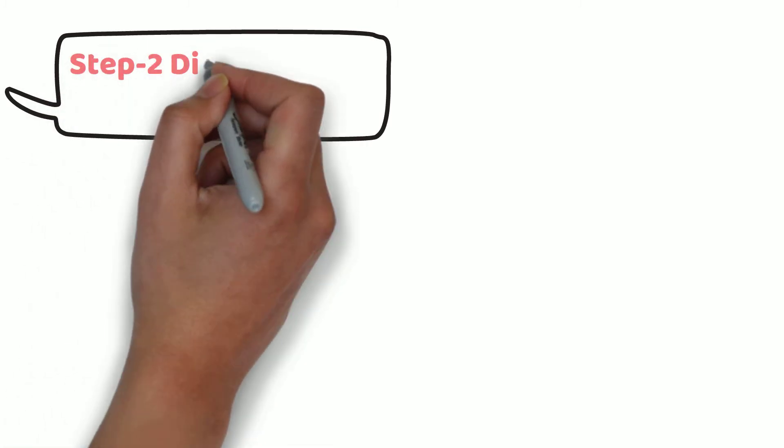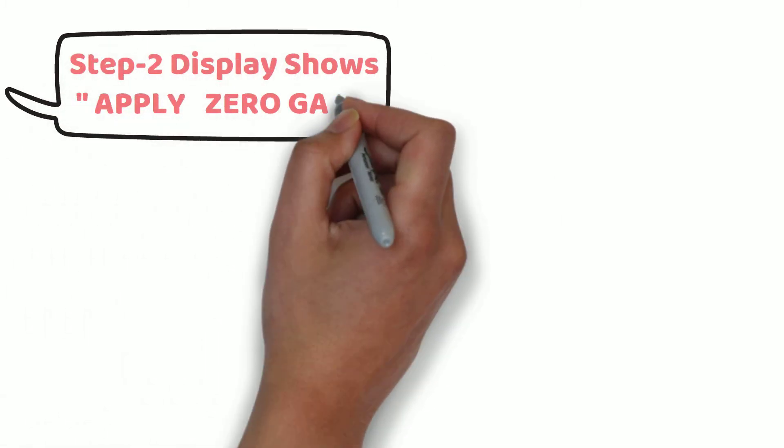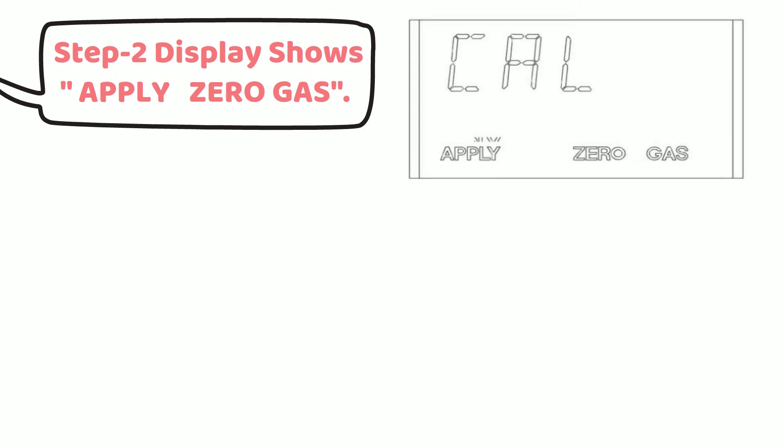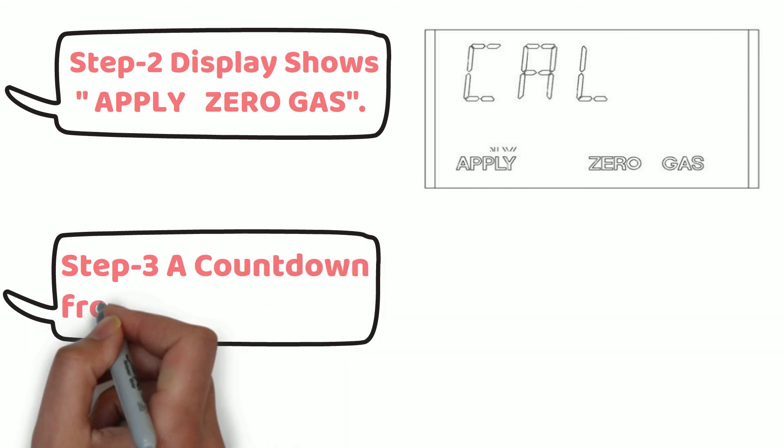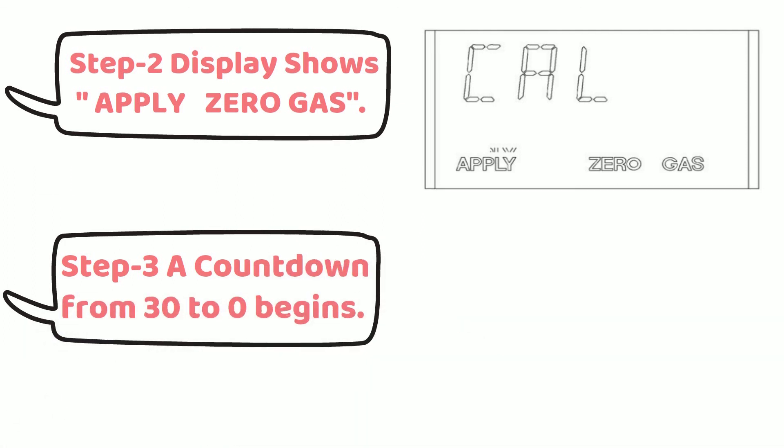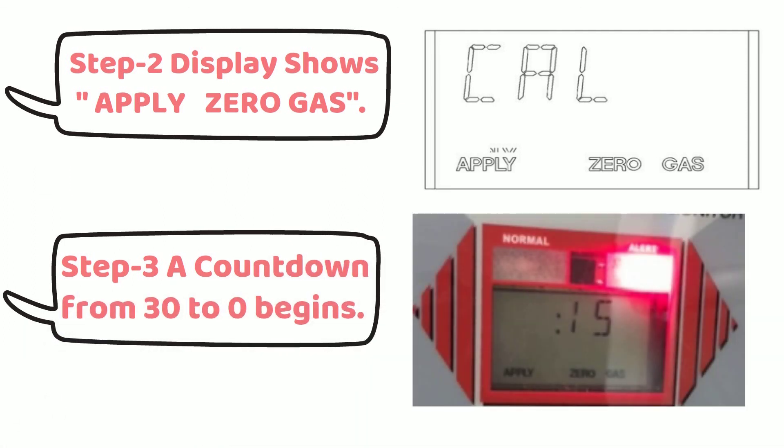You can see apply zero gas on controller display. After this, countdown from 30 to zero begins. Zero gas is not required if there is no gases presence in atmosphere where sensor is located. In this situation, zero calibration can be done in open to air. If there is some gases presence in atmosphere, then zero gas is required for zero calibration.